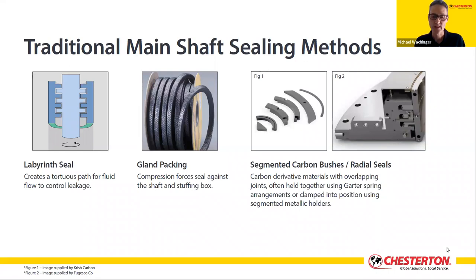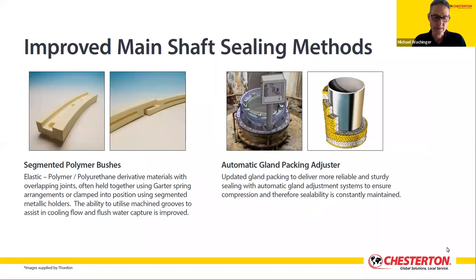For ease of installation and to assist in cooling water flow, the carbon and metal segments are made with overlaps held together with garter springs, particularly for radial seal designs, or metallic holders, particularly in axial seal designs. However, due to carbon being a softer material, the seal can wear out rather quickly. More recently, the high-wearing carbon segments have been replaced by elastic polymers and polyurethanes with machine grooving to assist in cooling flows. These materials are hard wearing yet still provide good sealing, but are still segmented and held together by the same traditional methods. Clean flushing water is still required to maintain abrasive-free cooling lubrication, and leakage into the turbine pit area can sometimes be significant.